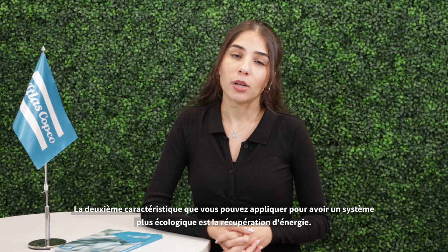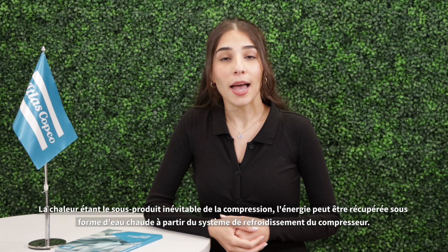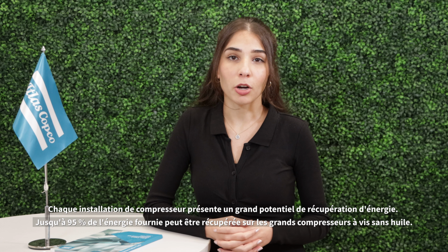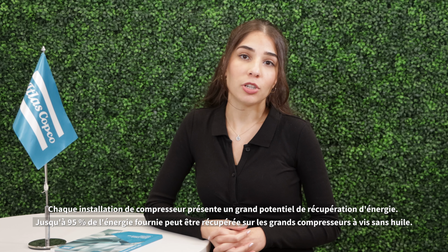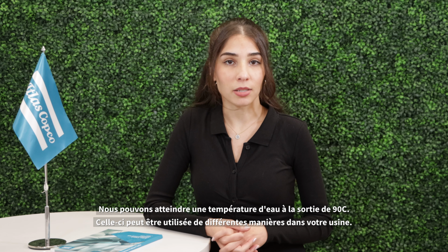The second feature you can apply to have a greener system is energy recovery. As heat is the unavoidable byproduct of compression, energy can be recovered in the form of hot water from the compressor cooling system. Each compressor installation has a large potential for energy recovery. Up to 95% of the supplied energy can be recovered from large oil-free screw compressors. We can achieve a water temperature at the outlet of 90 degrees Celsius.